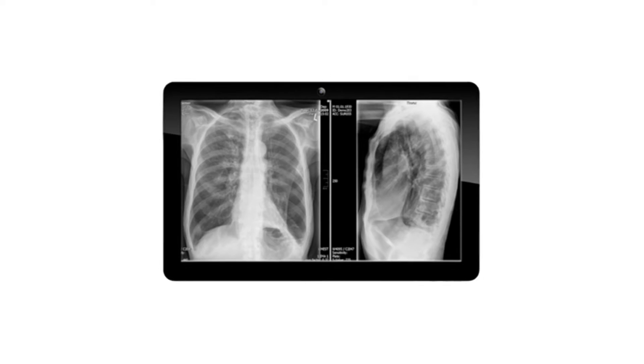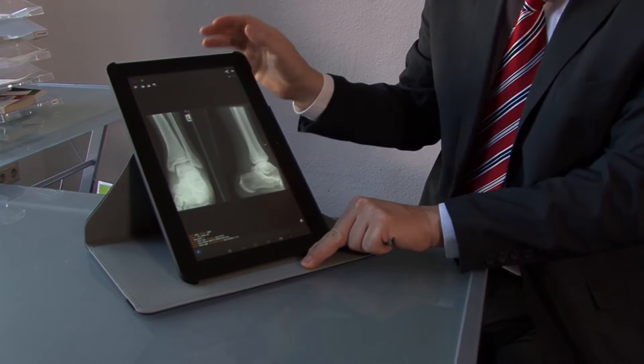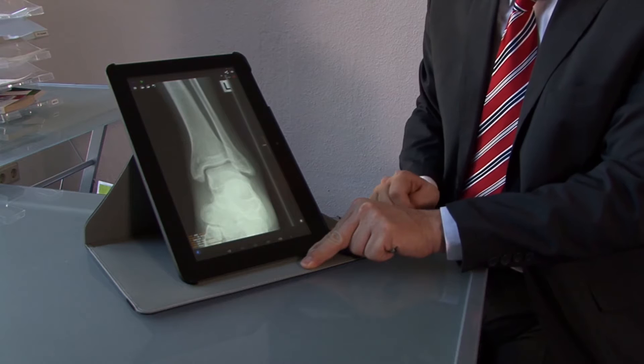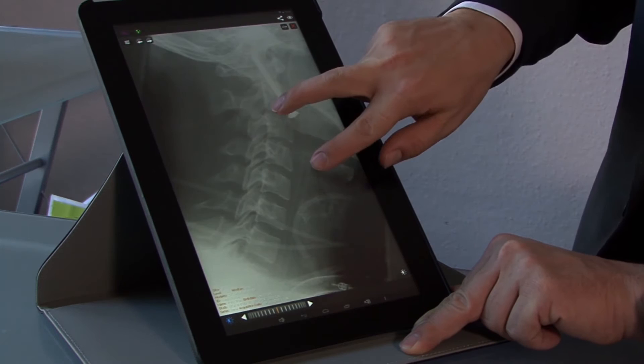We've worked according to the DICOM standard. We developed a so-called application-specific integrated circuit doing this kind of calibration. We patented it and implemented that into a tablet computer. A medical tool has different requirements — it needs to be secure, it needs to be fast. According to German regulations, a medical display needs to have a diagonal size of at least 13 inches.